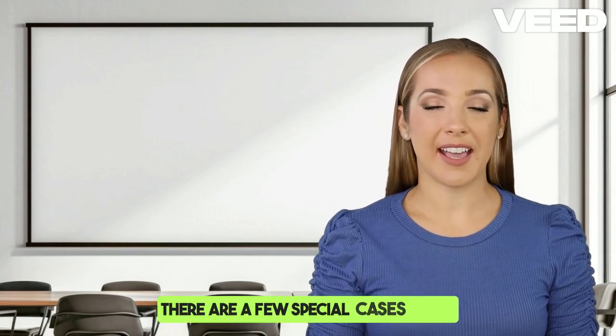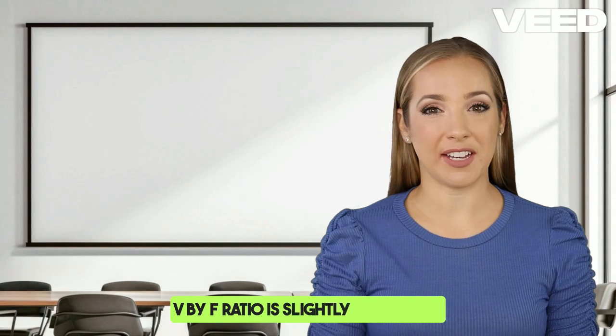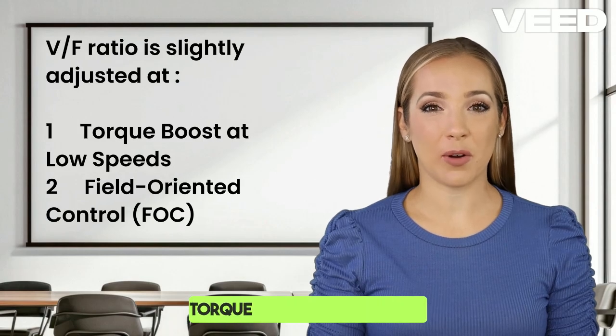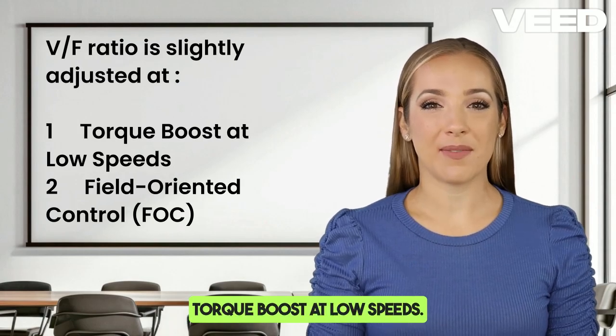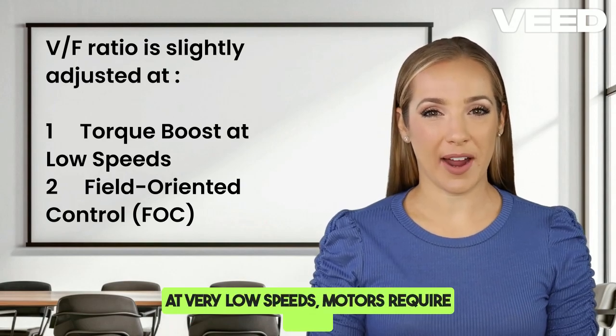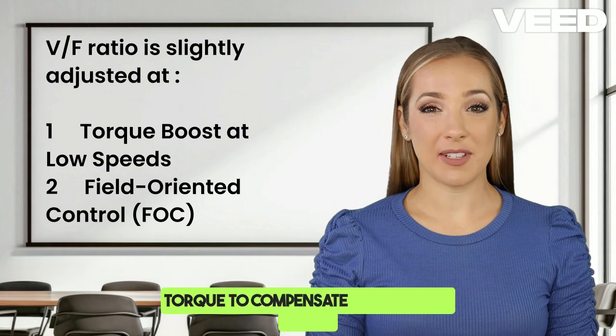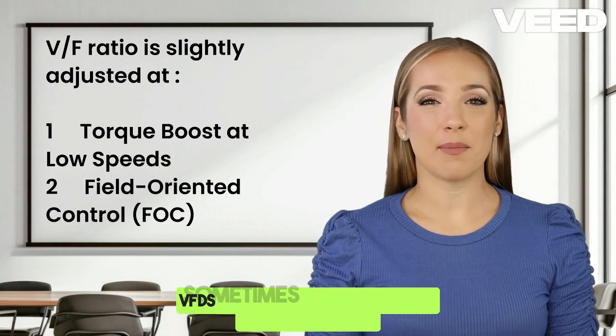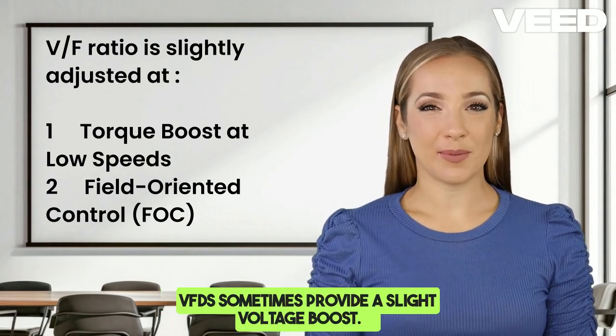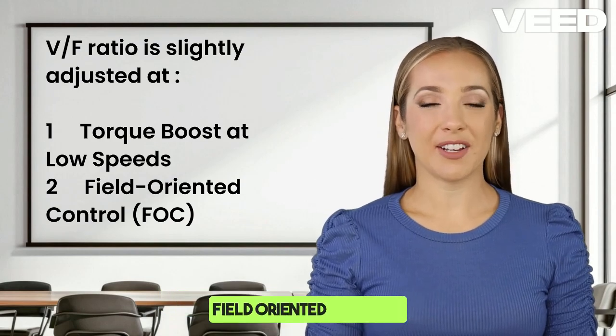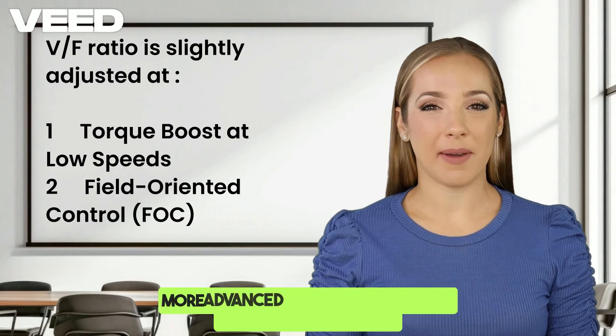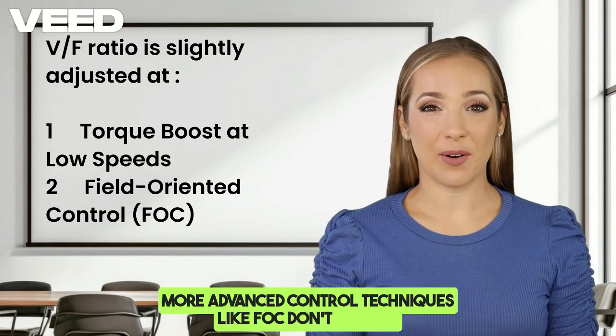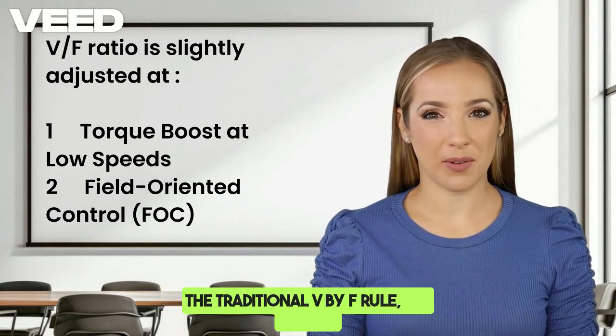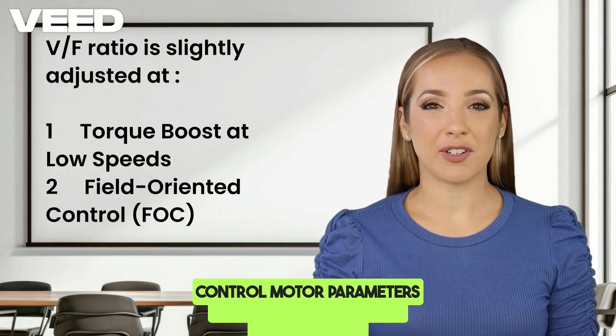There are a few special cases where the V by F ratio is slightly adjusted. One, torque boost at low speeds. At very low speeds, motors require more torque. To compensate for voltage drops, VFDs sometimes provide a slight voltage boost. Two, field-oriented control, FOC. More advanced control techniques like FOC don't follow the traditional V by F rule, but instead control motor parameters dynamically for better performance.